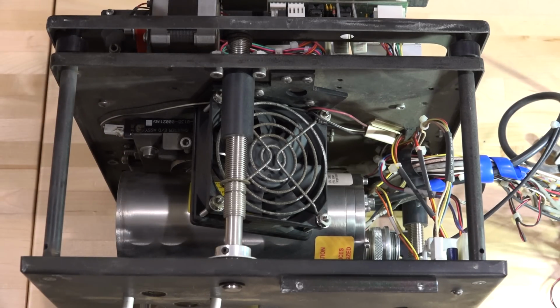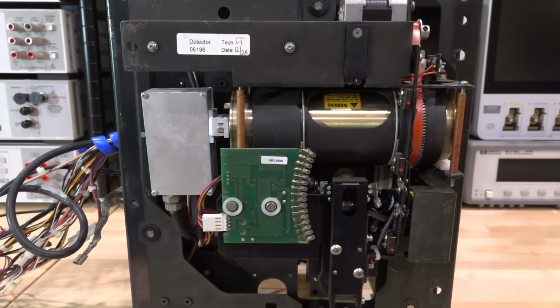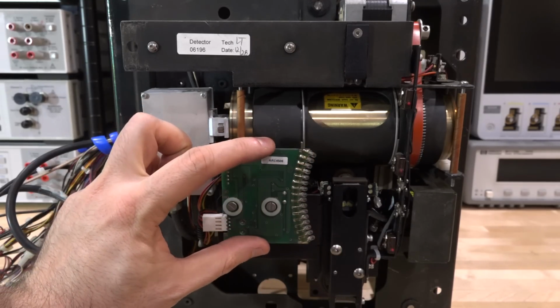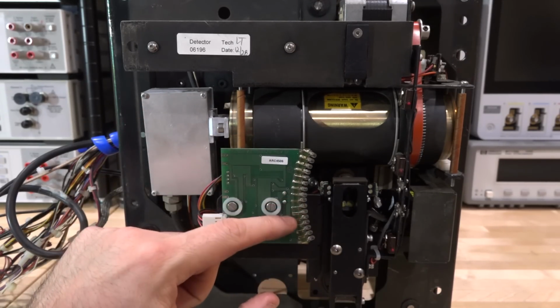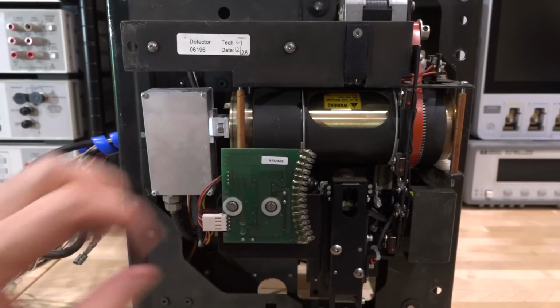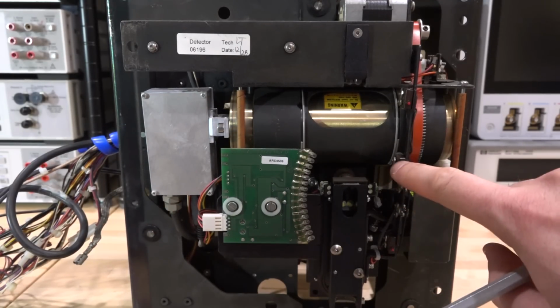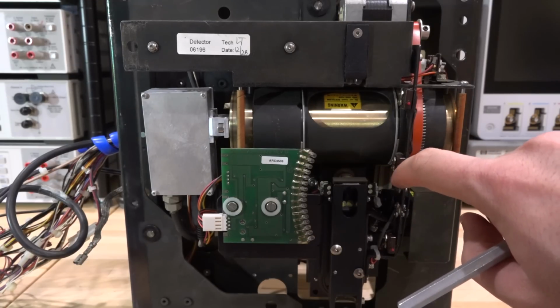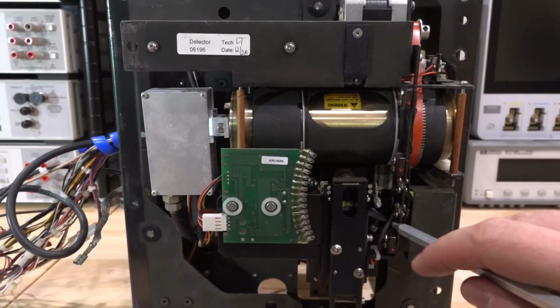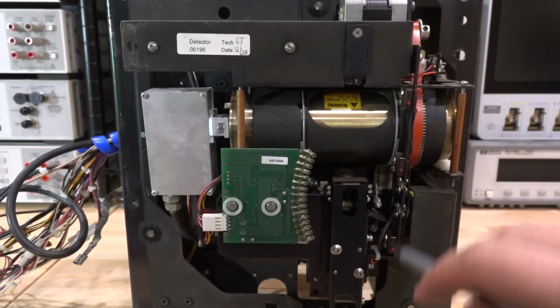Now let's look at the fun thing, which is the front. And here's a part of the instrument that faces the sample. And there are so many detectors and sensors, both optically and mechanically, to make sure that this is not colliding with the sample, as well as tell its proximity to whatever it is that you're trying to measure. Even this board over here with all these LEDs on it is on a spring, so that when you press, there's a button on the other side, so you know that you're hitting something. There's switches here, here, here, and this one is actually broken, so I think something must have hit it at some point. And there are IR detectors all over the place.